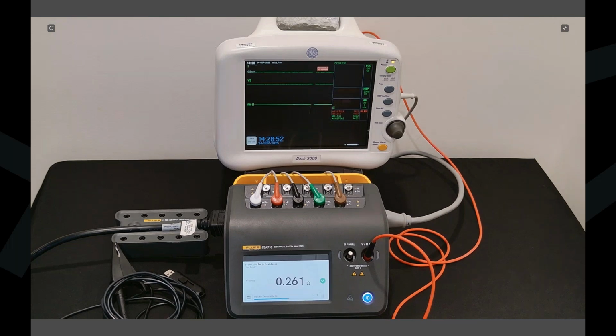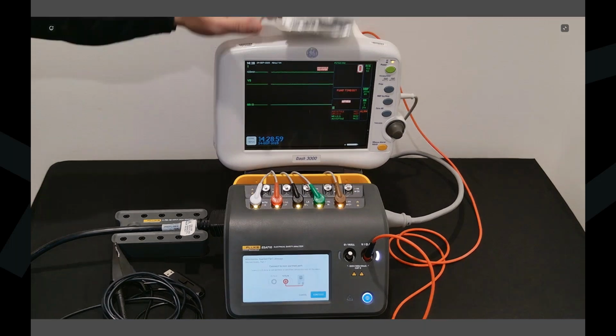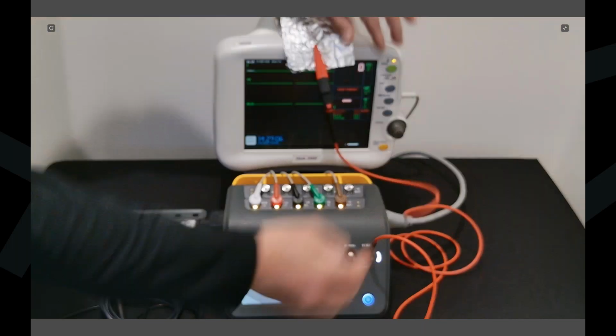Now it's going to our applied parts. It lets me know we're going to do on our applied parts, and we need to go to a non-earth. So here's where I got my foil. You would simply just come to a non-earth ground, connect to your foil. Let me do a quick reset. There we go. Color indication letting you know that there's power being applied to the device under test and to not touch your applied parts. But again, everybody look, I'm not advancing anything. The instrument is doing this all through optimized procedure building within OneQA on the instrument. That's why our ESA700 is one of the smartest instruments that we have in our lineup.